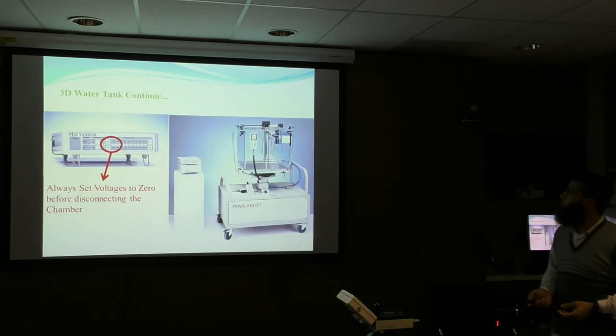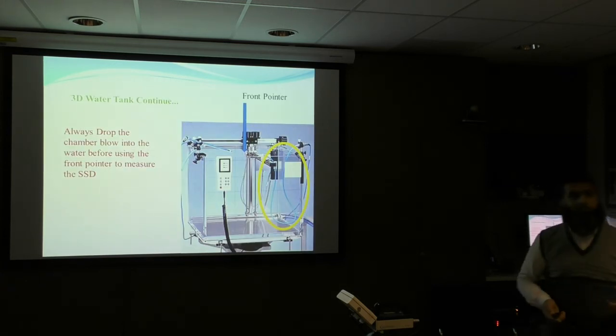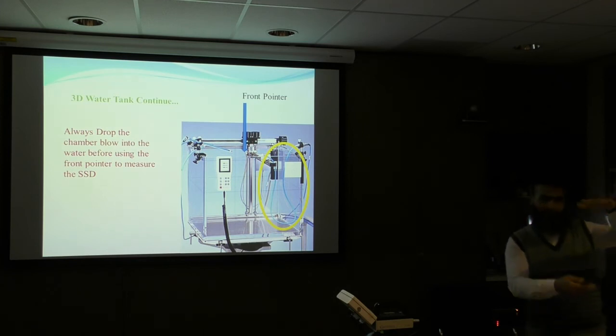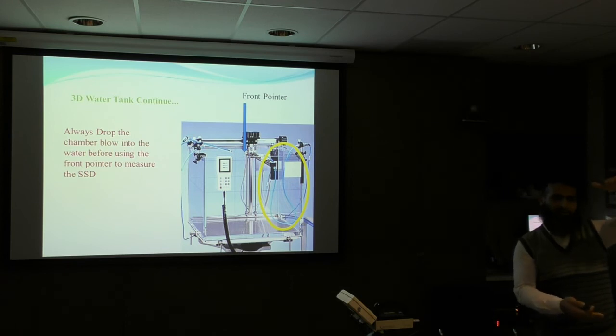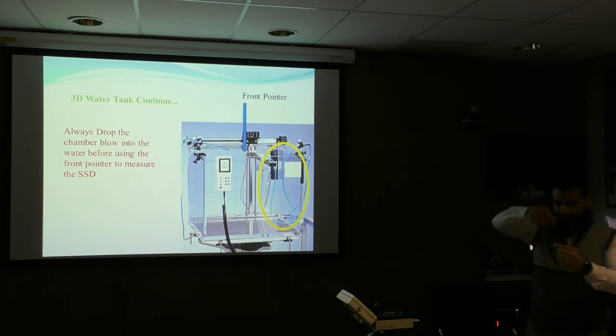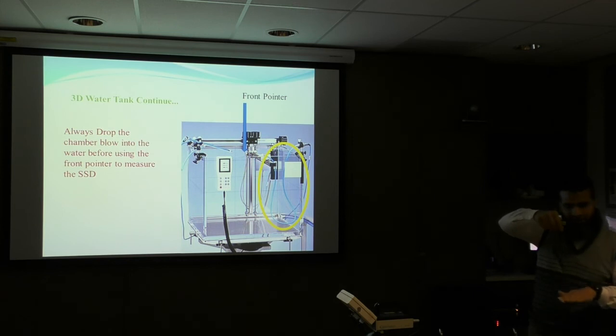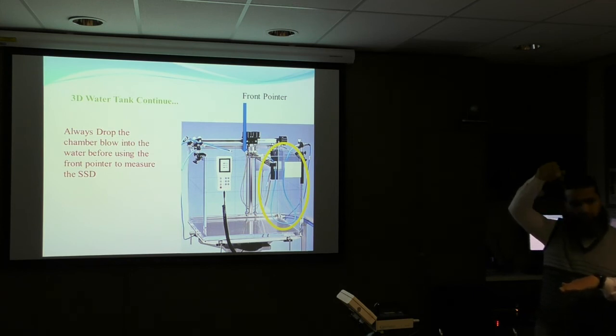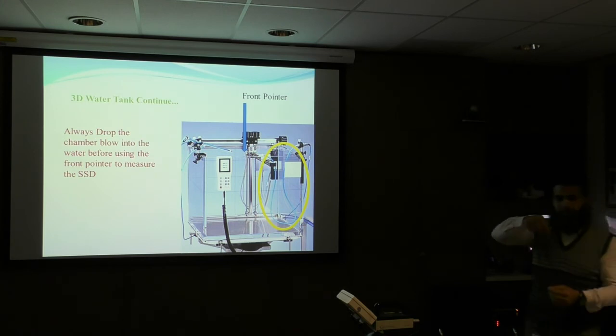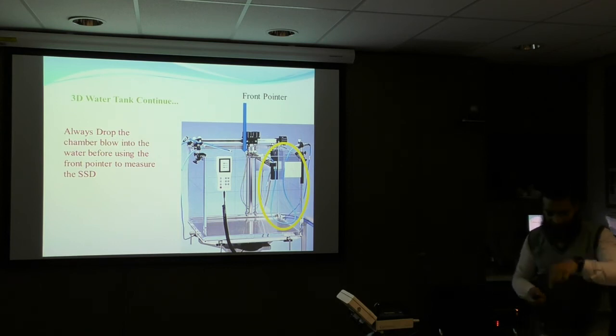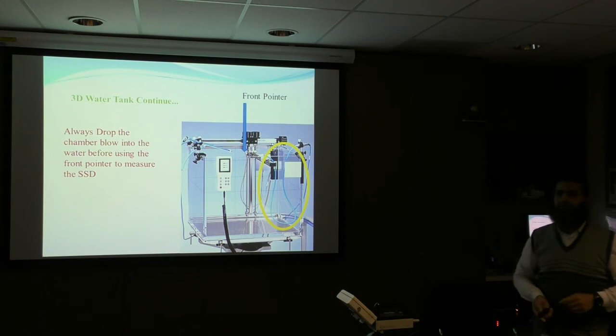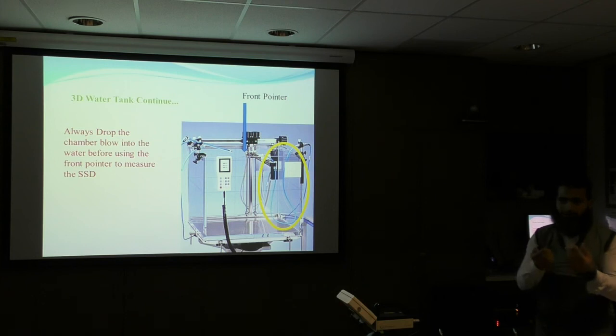Another thing regarding front pointers - you've heard about SSD, source to surface distance. When you put the front pointer to measure the height of the water surface from the source, if it is mishandled and falls off on the water tank and the chamber is exactly underneath, it can damage the chamber straight away, because it's quite heavy and chambers are very sensitive and very small.